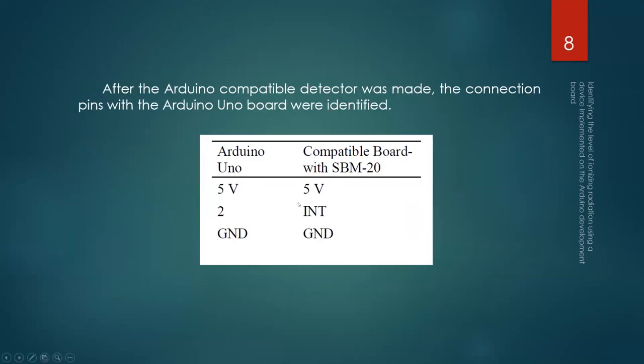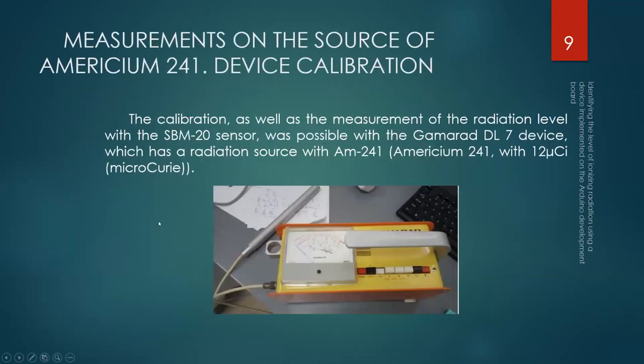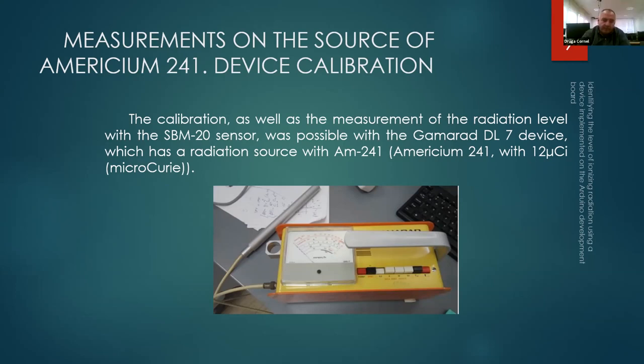After constructing this simple and inexpensive device, the most important step was calibration. They calibrated the device using a source of americium, a radioactive element. For this calibration step, they used a reference dosimeter, which is presented here.